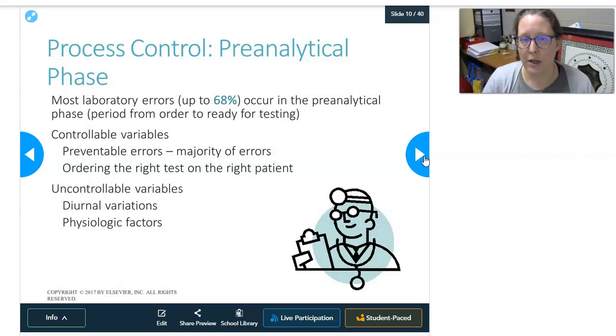And so we're going to now look at the whole process control of testing, and we're going to start, obviously, with the pre-analytical phase. So most lab errors, up to 68% of lab errors, will occur in the pre-analytical phase, which is the period from the time a test is ordered, or from even just ordering the test, to the time the sample is ready for testing, and then we would enter the analytical phase. There are variables that are controllable and variables that are not controllable. And your controllable variables are obviously where all the preventable errors are, which is where the majority of errors would lie.